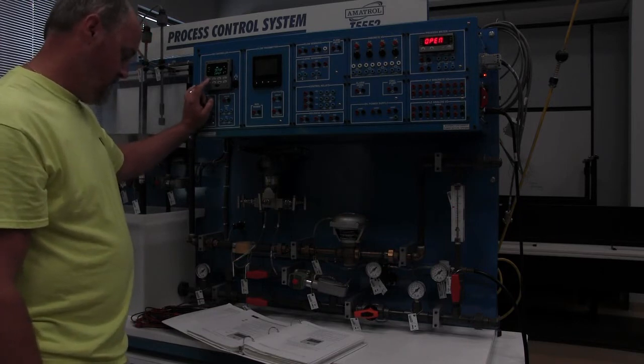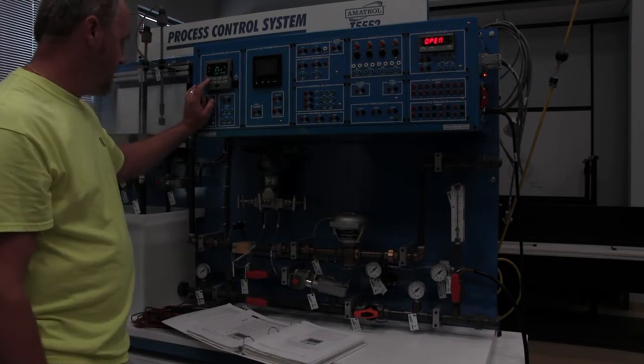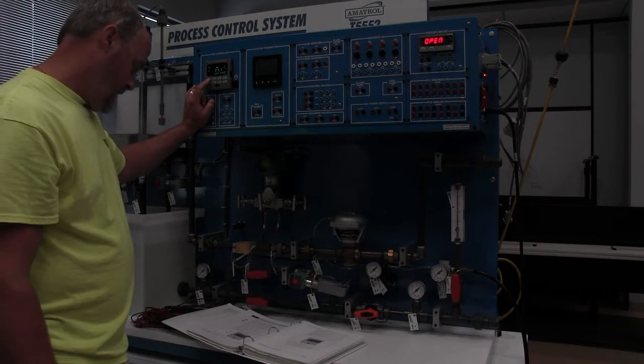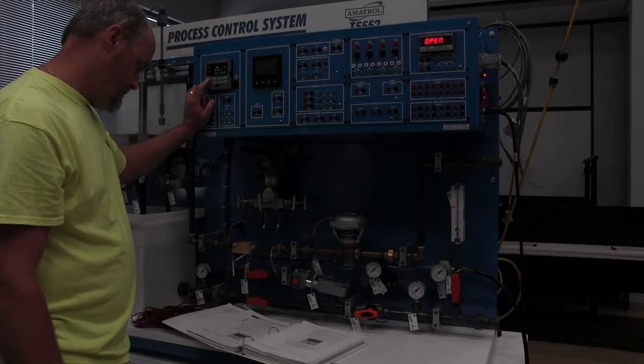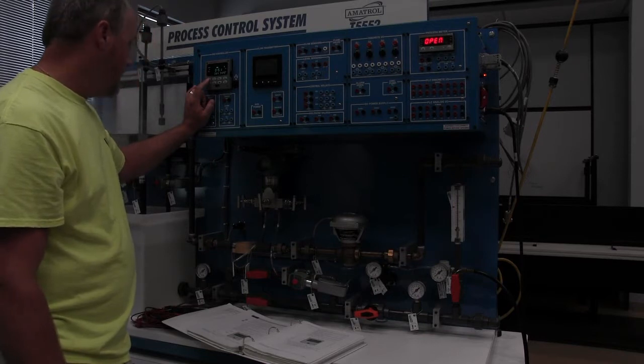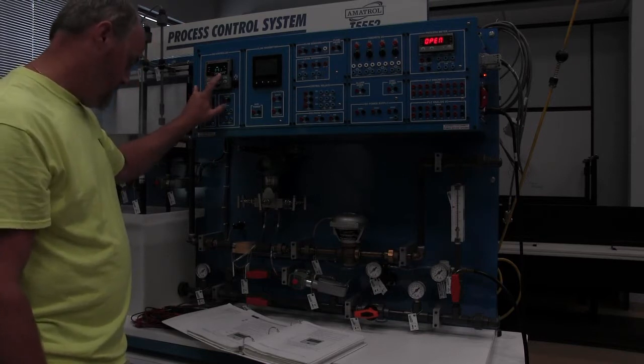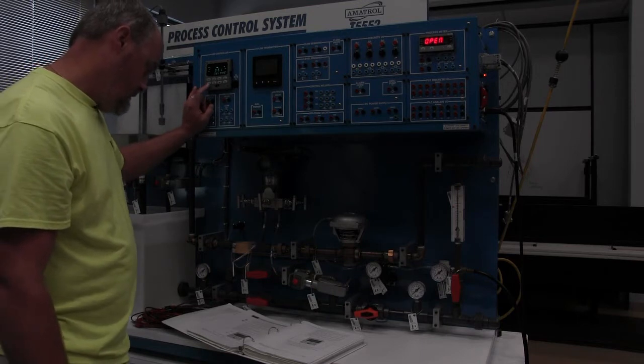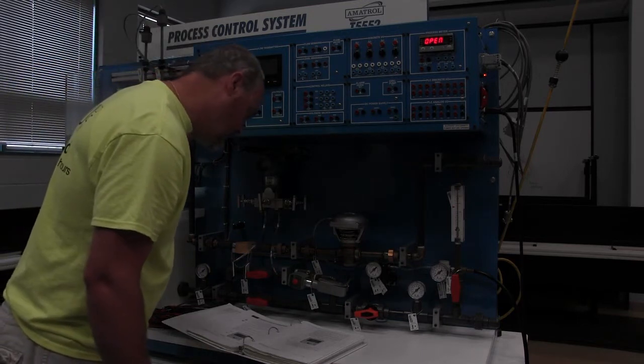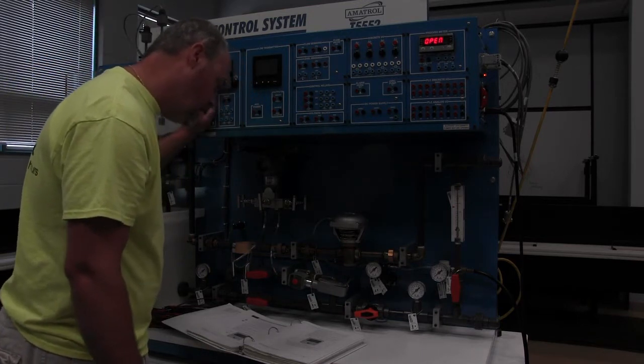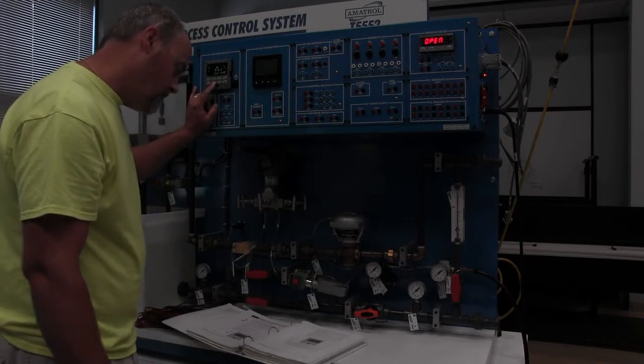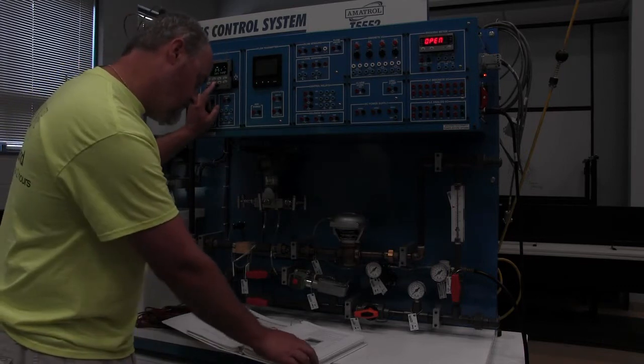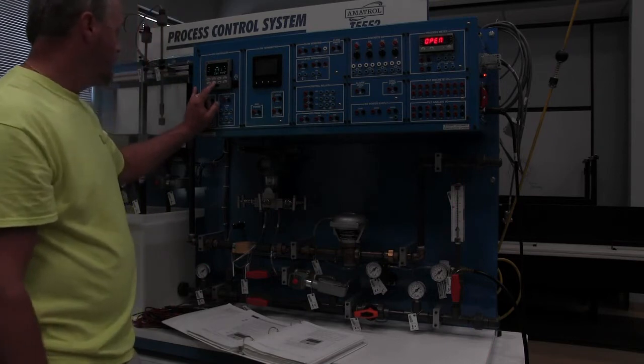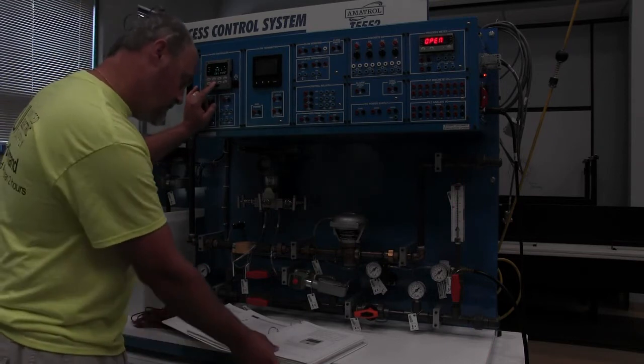Once we're there, we're going to press the function loop half key 1 time. And the controller displays the first parameter, input 1 parameter, IN1 type. And we're going to press the up or down keys to scroll, and once the setting is returned, you get 1.5 volts. So we're going to change this to 1.5 volts.